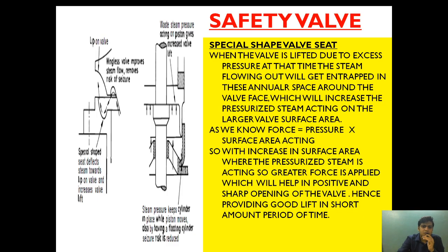Basically, what is happening, as you can see in a closer look, this waste steam is coming from here, this is the floating cylinder and this is the waste steam. This is the bottom spring carrier and this is the spring. When the waste steam is coming here, acting on the top of the surface, if the dirt accumulation is here in between, this thing is floating in nature, so once it is compressed, this thing will also come with it, preventing any further hindrance.